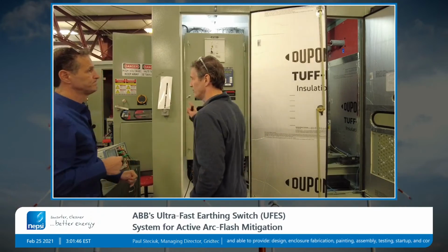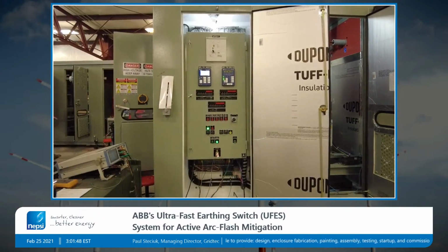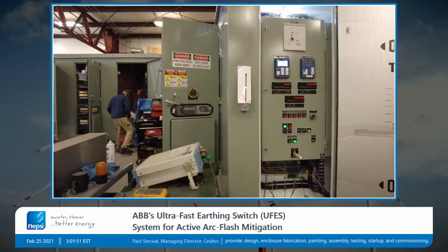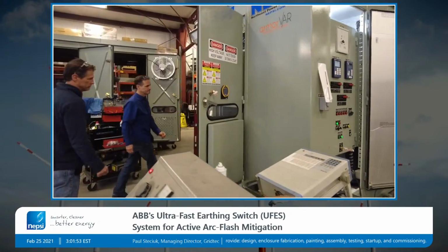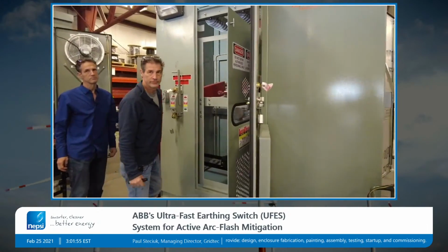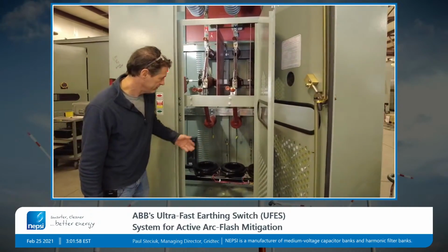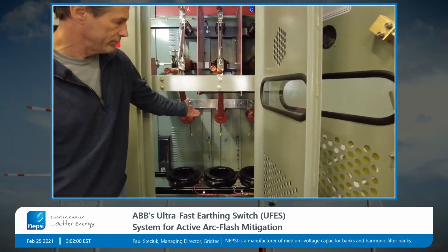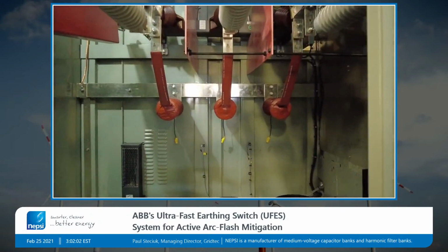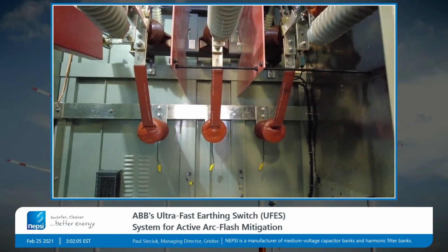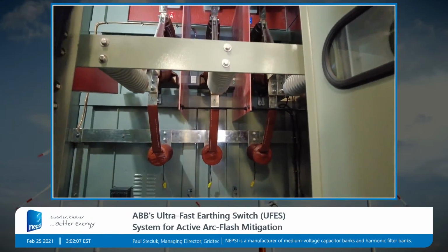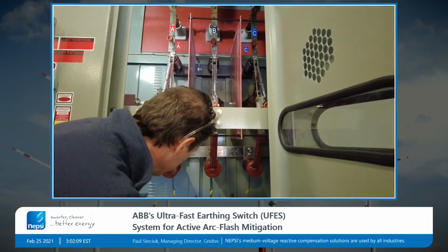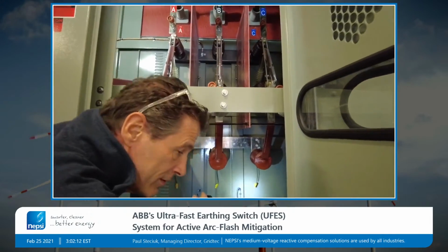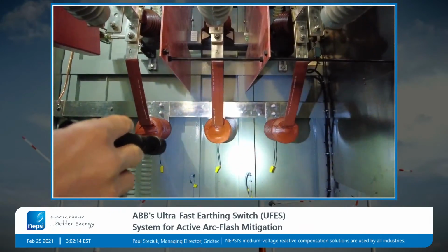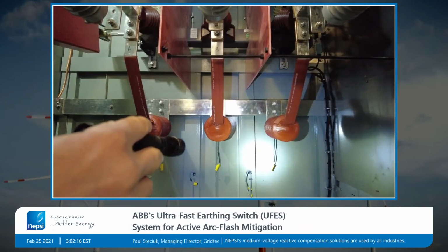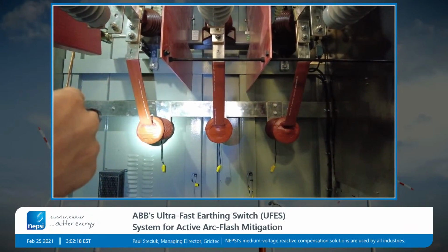All right, why don't we start here, with the primary switching elements. The UFES system starts with the primary switching elements. These are the devices that will put a direct short onto the bus bars if the system detects a fault with light and current. So on here we have 3 connections. They are disconnected right now. Those are the cables that will activate these 3 primary switching elements.